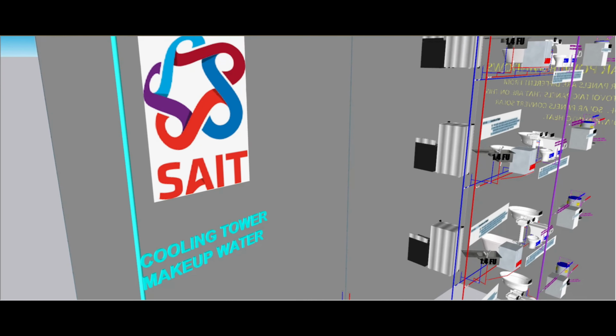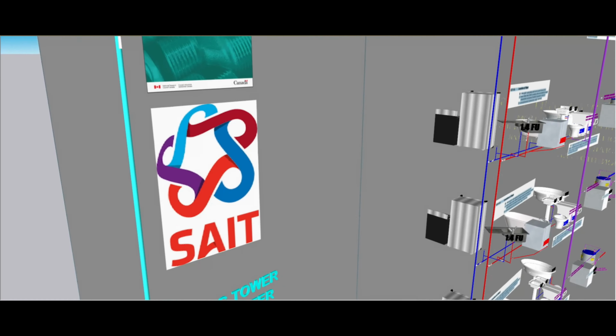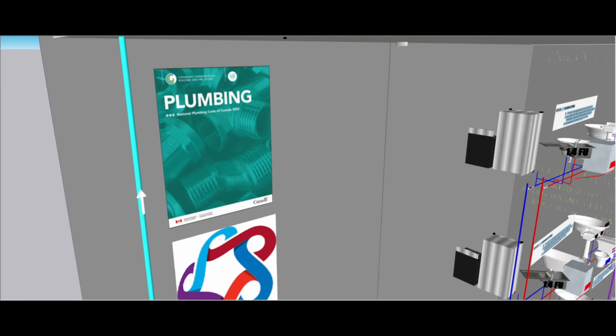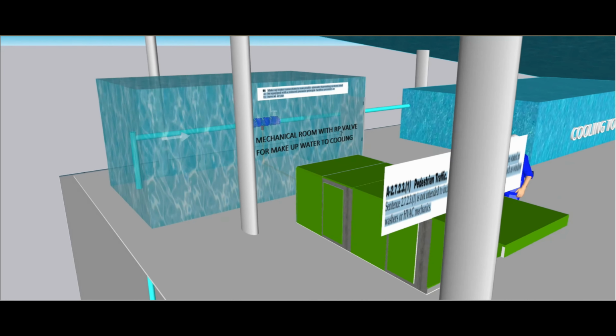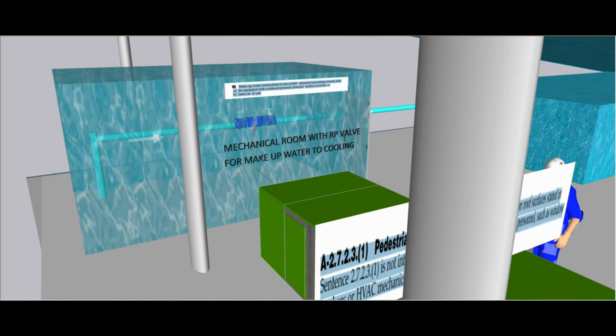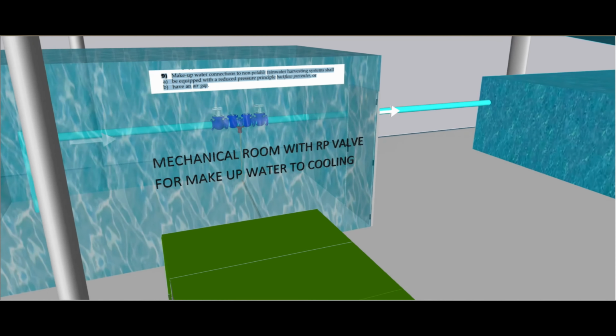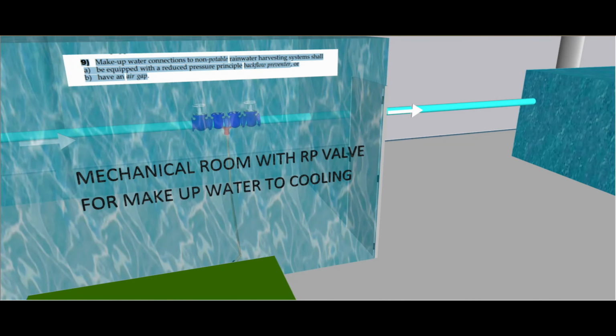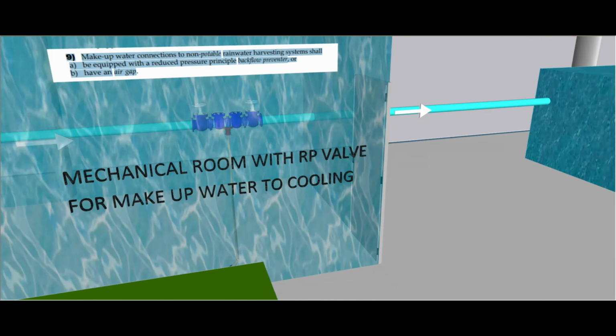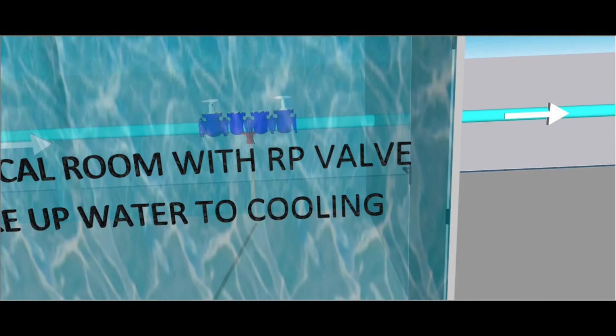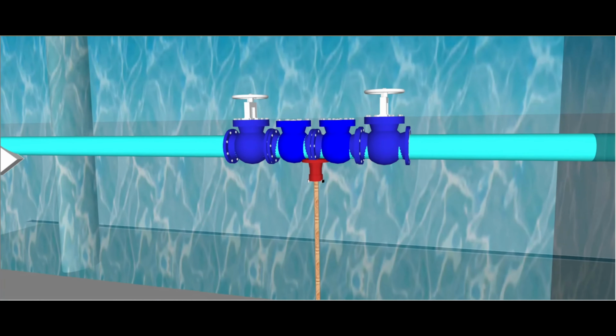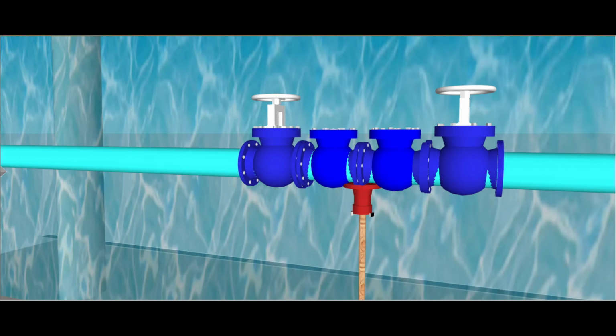And it'll feed into my little mechanical room on the roof, which has an RP in it, because it says here in subsection 9: make-up water connections to non-potable rainwater harvesting systems shall be equipped with an RP or have an air gap. So there is our RP, and then it feeds into the cooling tower. So we're using treated rainwater to feed our cooling tower, which is pretty cool.